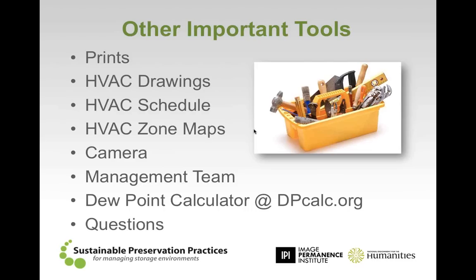One thing I recommend, every job I walk on, every project we walk on, the first time we walk in to see the air handling systems, we actually sit down and do a hand drawing. They're not great. I'm not trying to be the next Walt Disney. They're just a simple line sketch of how the system operates. It helps you understand the moving parts of the system: what controls what, what's the order of this system, and how it all works together.